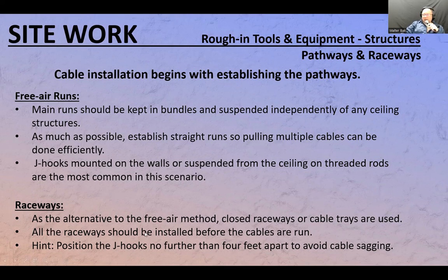Raceways, as the alternative to the free air method, closed raceways or cable trays are used. All the raceways should be installed before cables are run. Hint: position the J-hooks no further than 4 feet apart to avoid sagging.